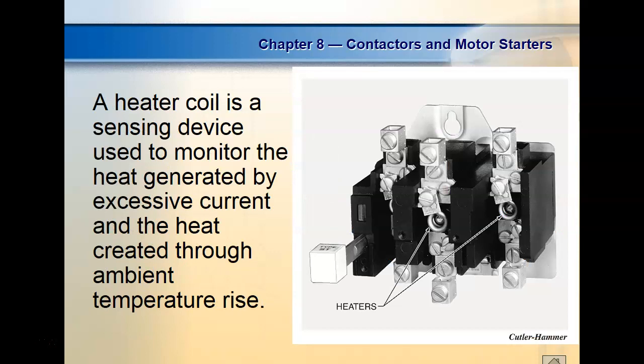We use what we call a heater overload. The heater coil is a sensing device used to monitor the heat generated by excessive current and the heat created through ambient temperature. So these guys basically work off heat. What we're going to do, guys, is have our motor starter on there. One of the things we're going to do with our motor is call it single phase loss.